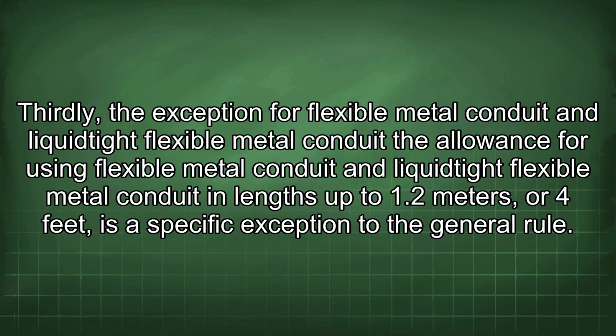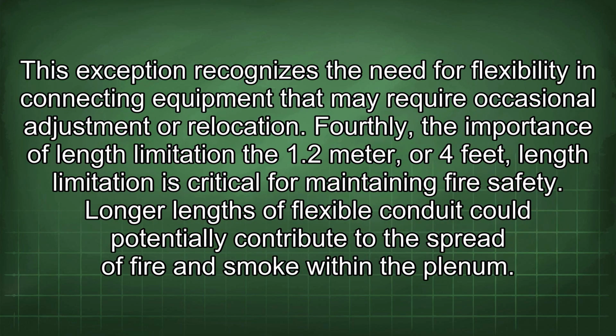Thirdly, the exception for flexible metal conduit and liquidtight flexible metal conduit. The allowance for using flexible metal conduit and liquidtight flexible metal conduit in lengths up to 1.2 meters or 4 feet is a specific exception to the general rule. This exception recognizes the need for flexibility in connecting equipment that may require occasional adjustment or relocation. Fourthly, the importance of length limitation. The 1.2 meter or 4 feet length limitation is critical for maintaining fire safety. Longer lengths of flexible conduit could potentially contribute to the spread of fire and smoke within the plenum.